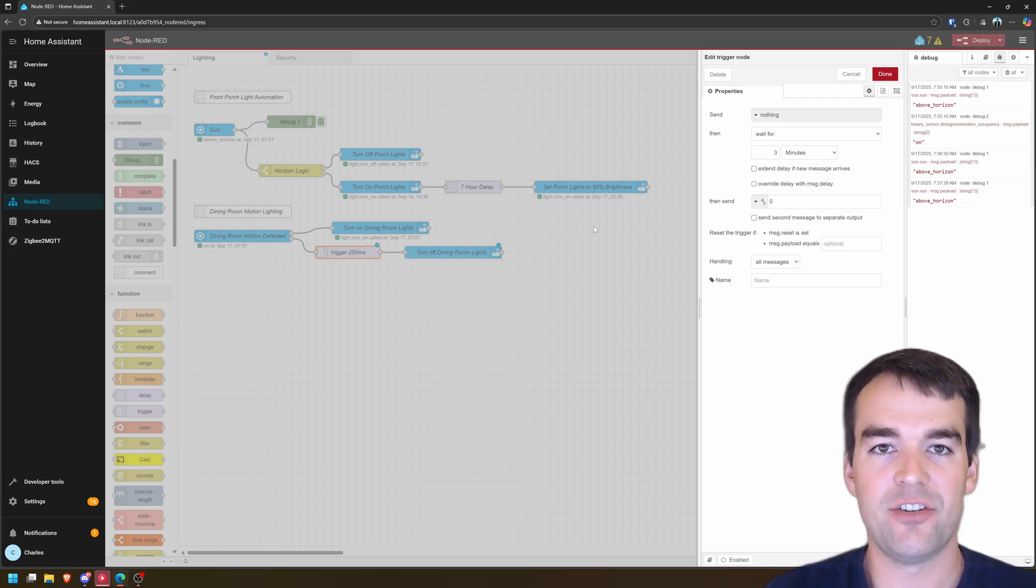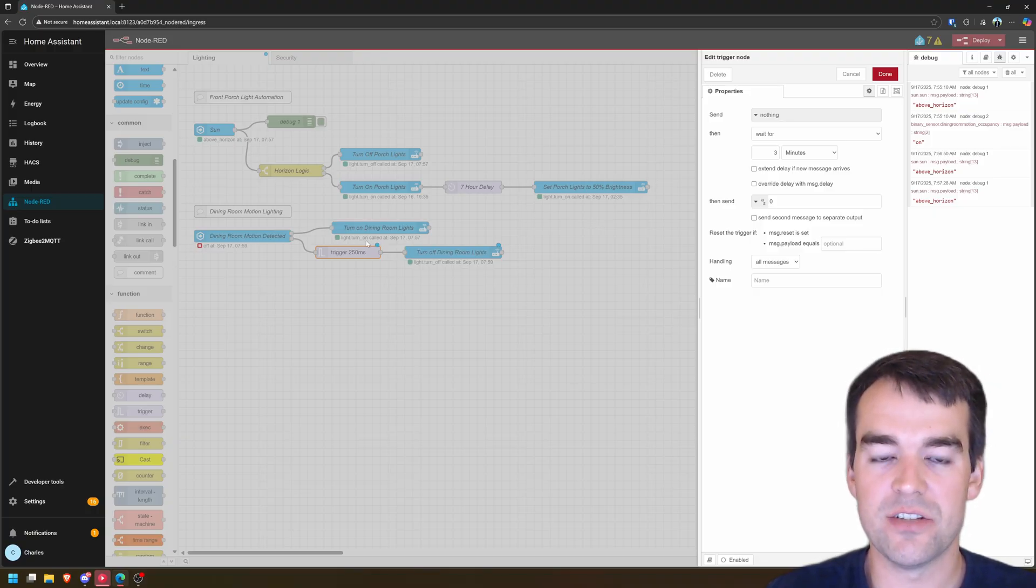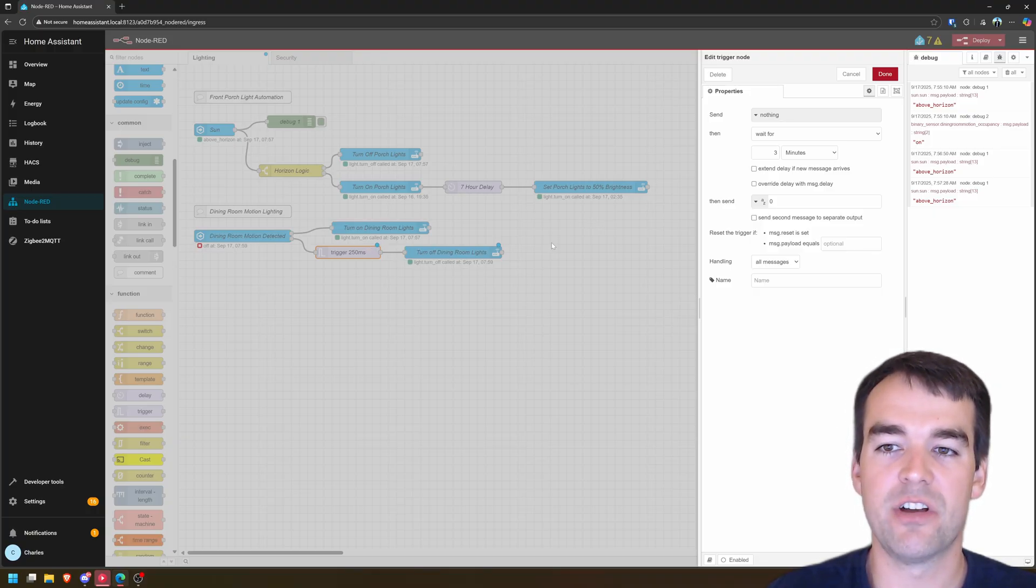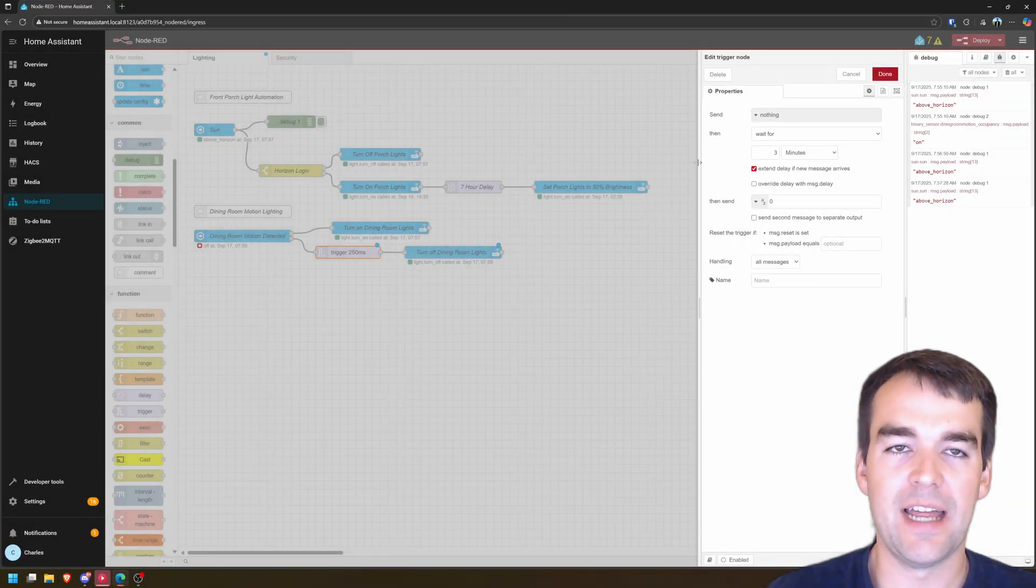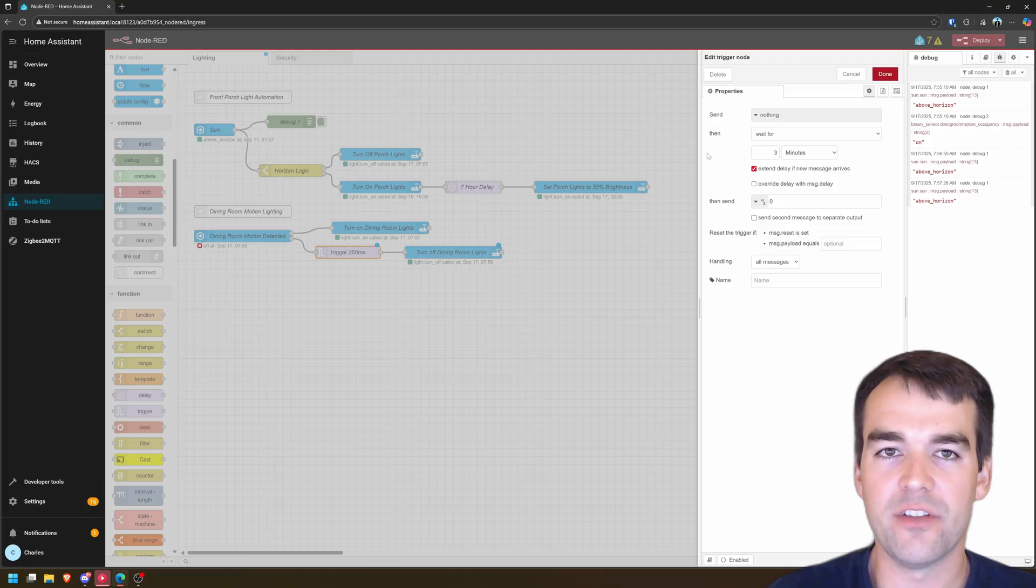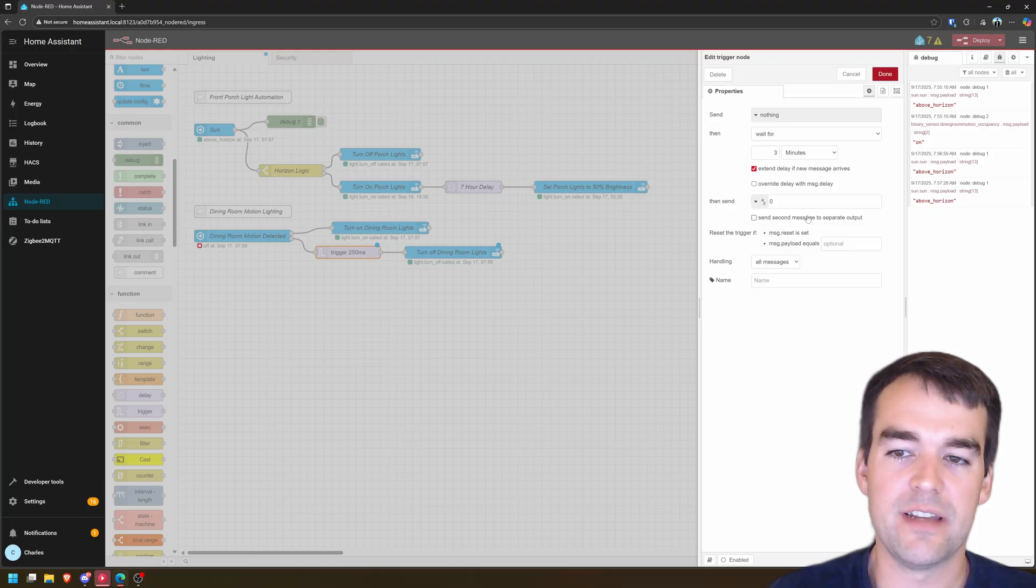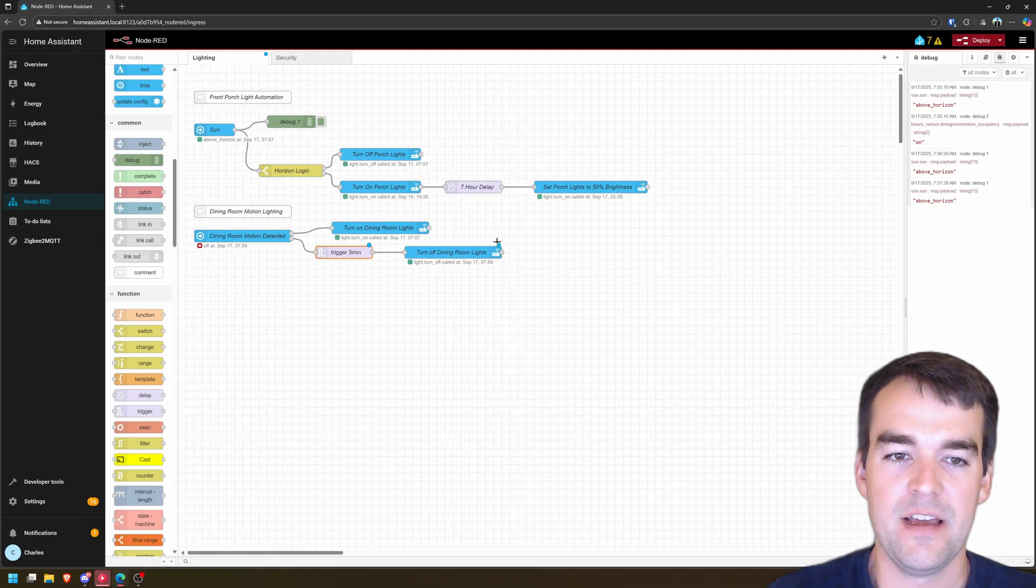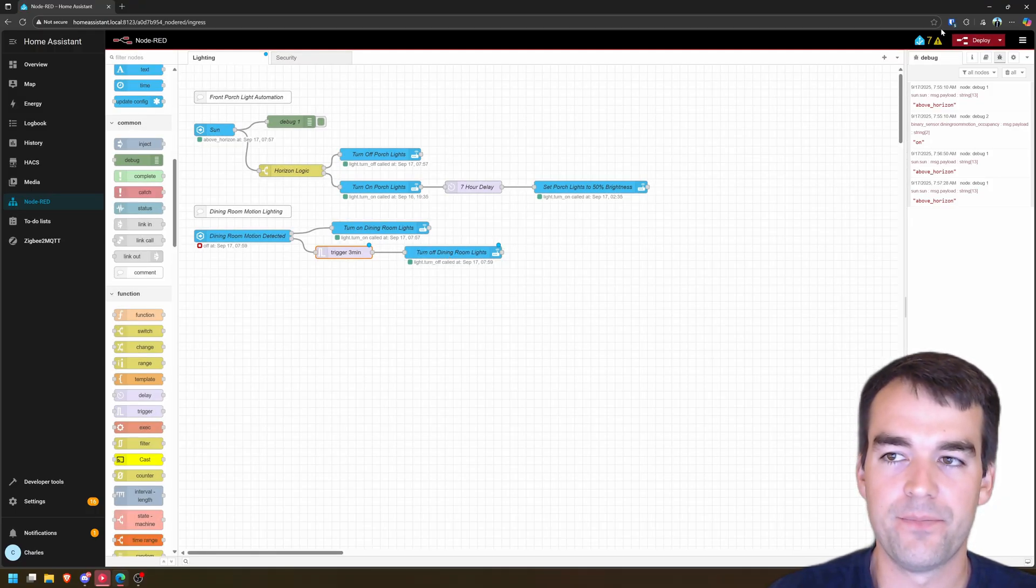I like three minutes because it's relatively quick, but it's also relatively forgiving. If you're in an area where you need to adjust this up to five minutes or down to one minute, you can. But this is on top of that 90 second default timer that this motion sensor has. So 90 seconds after you leave the room, it says nobody's here anymore. It sends that message to this trigger and the trigger then waits for three minutes.